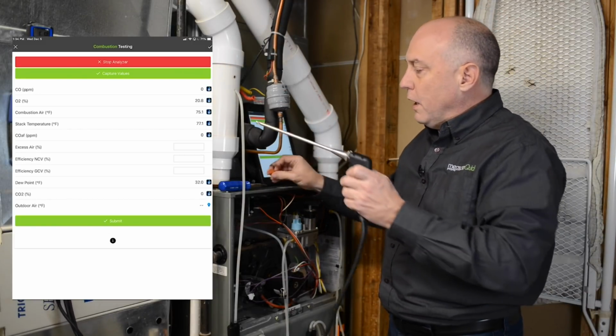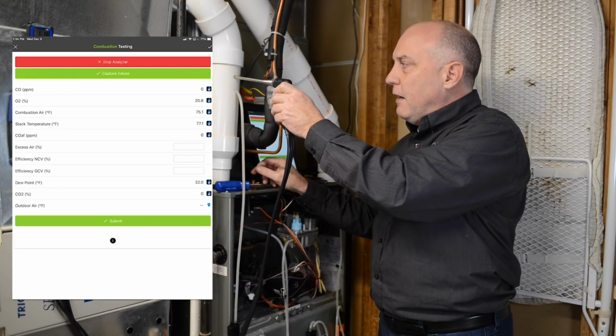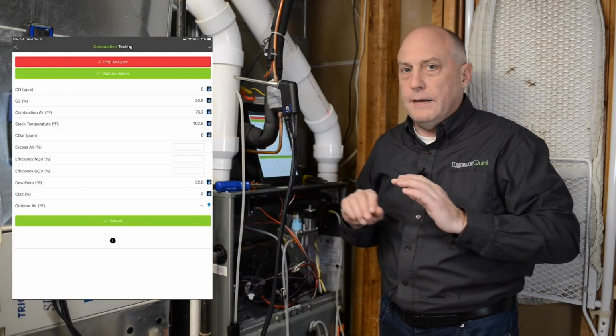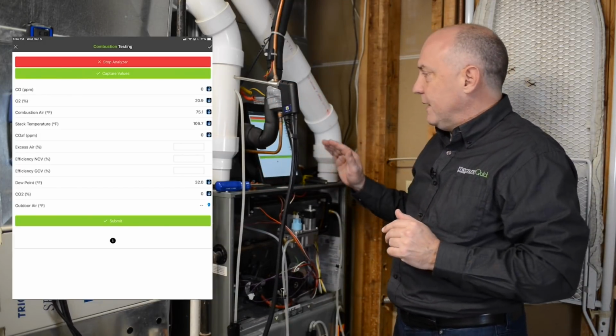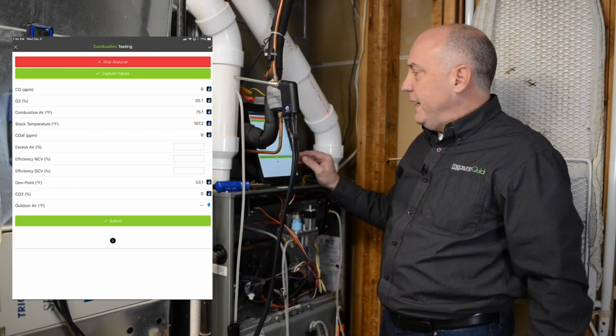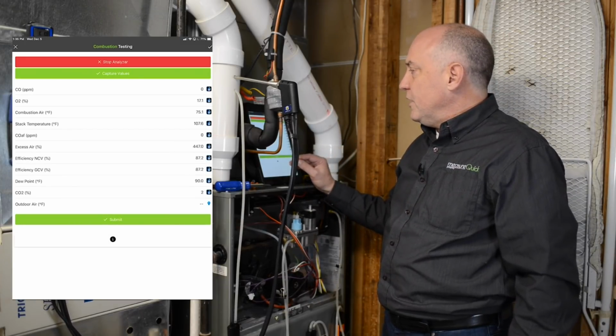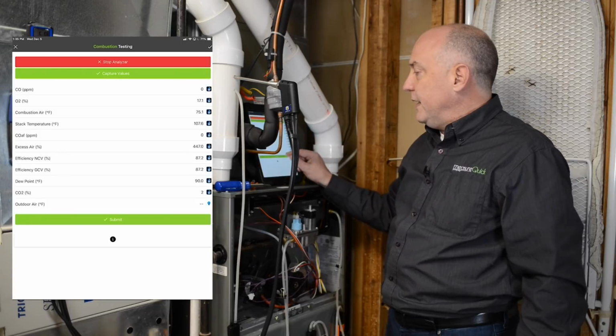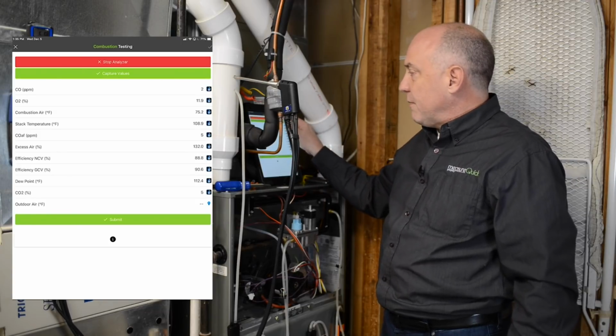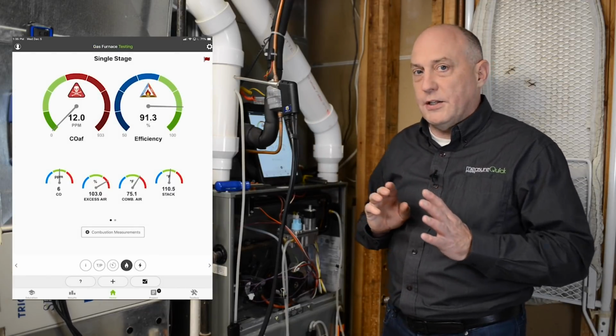I'm going to pull out my plug for testing here, slide my analyzer in, pull it back about halfway, and now I'm going to let that go for some testing. It's going to take a few seconds for the readings to start coming in, but we'll start seeing our CO, O2. Now you can see those readings start coming in, and I'm just going to hit the check mark at the top here, and we'll start watching it on the display.